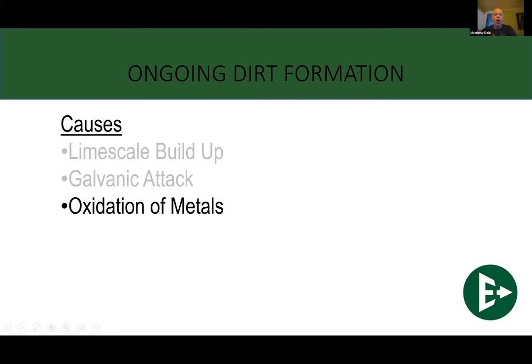Okay, ongoing dirt formation. Now, this is what I'm talking about. We can get the dirt out pretty easily. We just be cognizant of what we're doing, give it a flush, and that will take care of the vast majority of the dirt that comes with the initial creation of a system. Then we have the dirt formation during system operation. We'll get to the lime scale or the scaling buildup, but what I really want to talk about is the oxidization of the ferrous metals inside of a system.